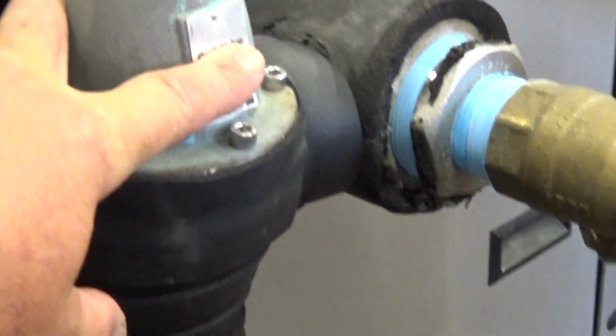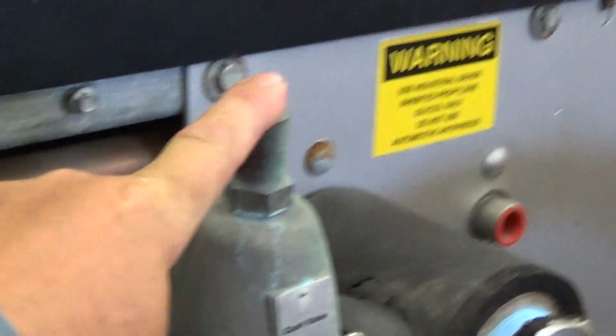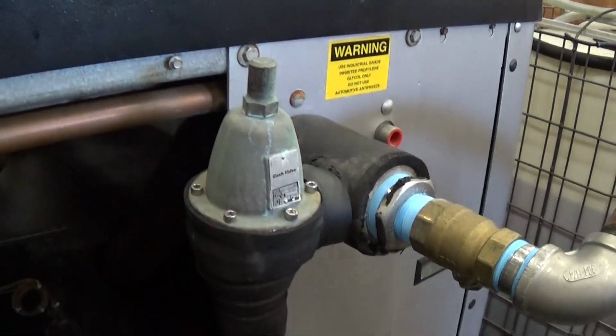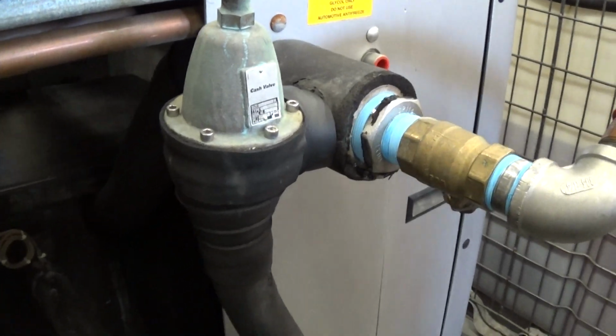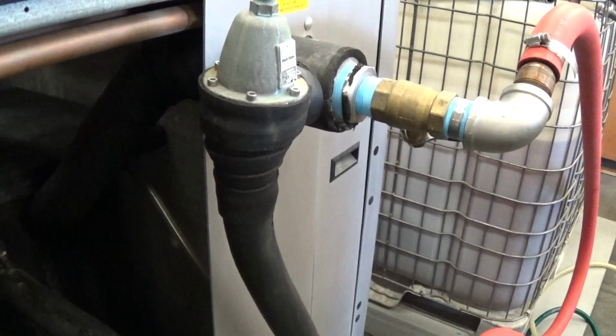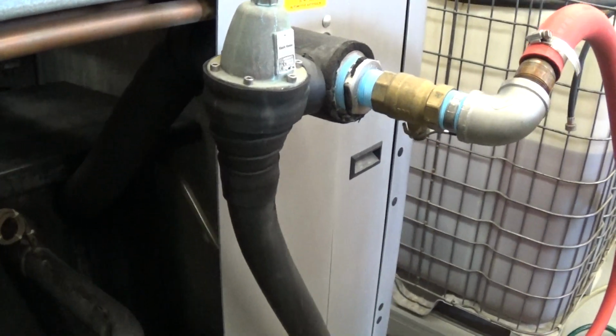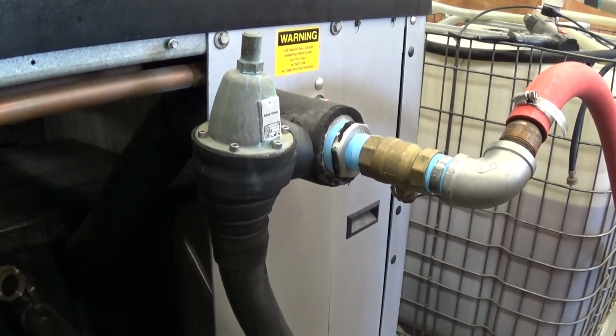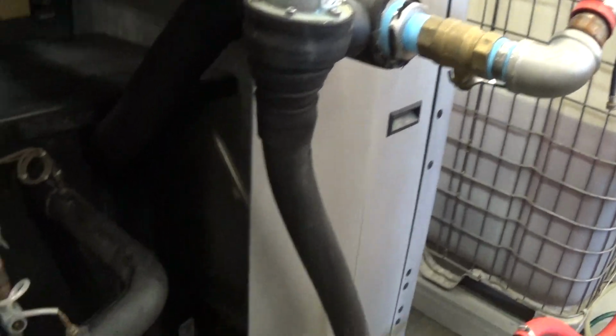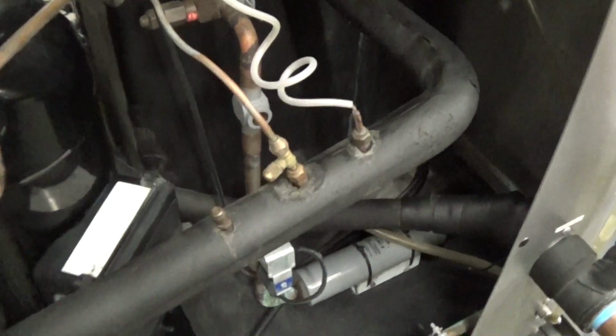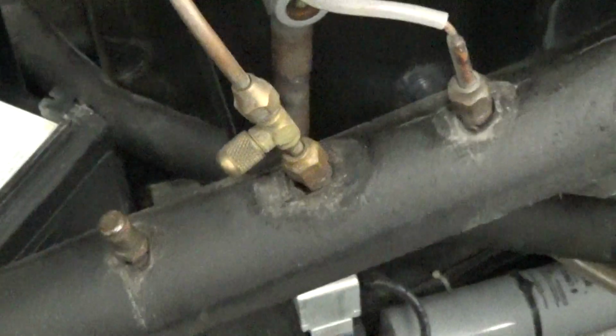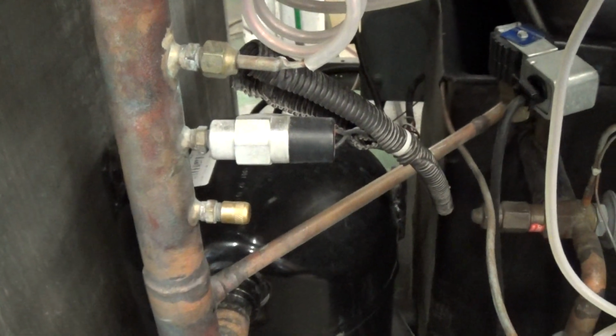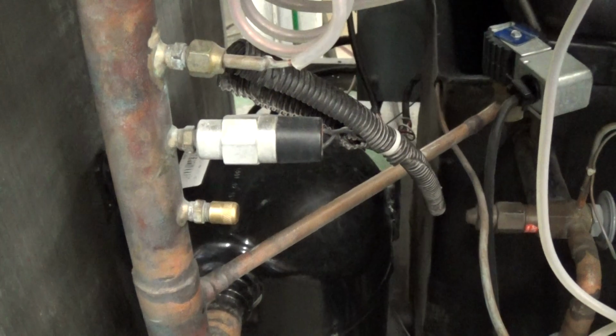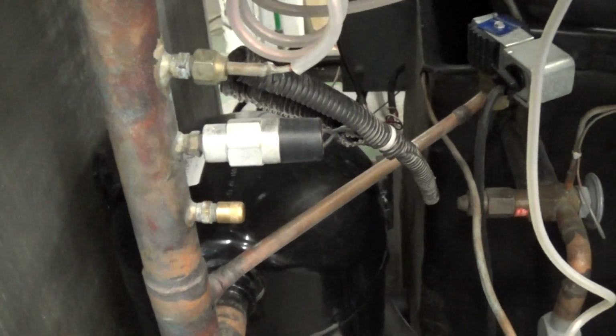The unit also has its own preset low flow bypass. So if out in the customer's process there's any solenoid valves or the process just stops or gets restricted at any time, the chiller will bypass flow back to itself. Here in the refrigerant line we have, well, that goes to one of the refrigerant gauges. This is our high pressure reset. It's an auto reset.